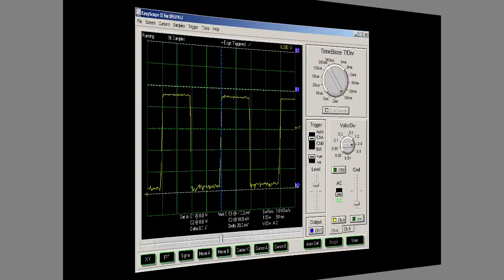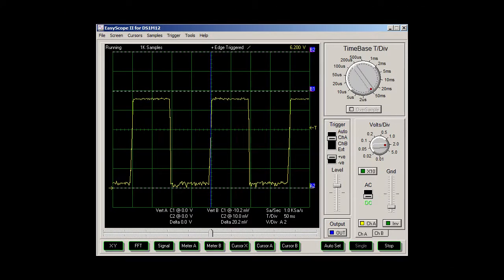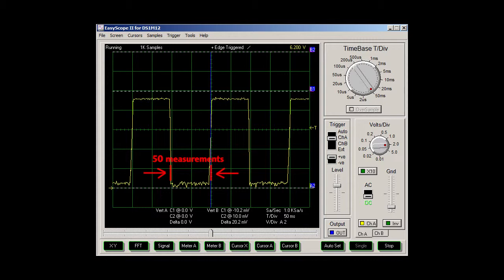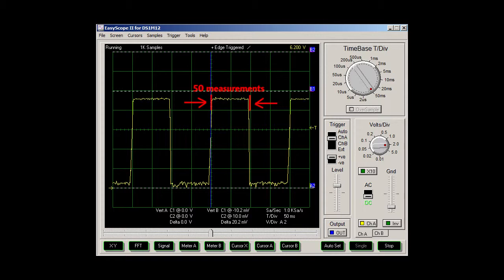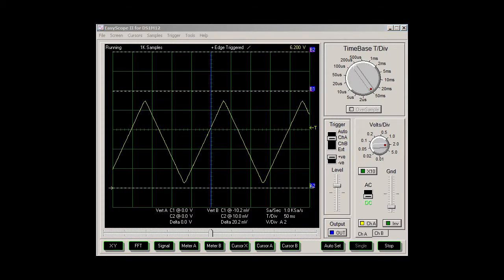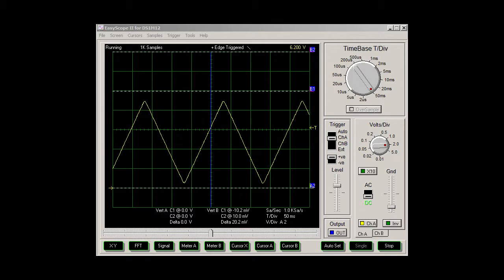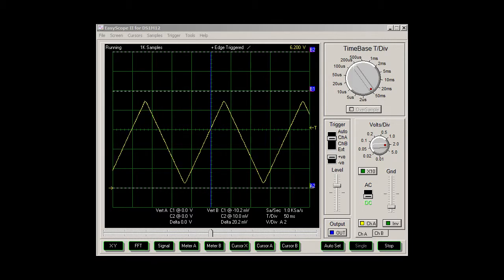If we use a filtering setting of 50 samples, then in this example there is only one time when we get a true low, when we average these 50 measurements, and only one time when we get a true maximum value, when we average these 50 measurements. The rest of the time we get something in between. So now our output looks like this triangular waveform when a square object passes by, all because we averaged so many samples.